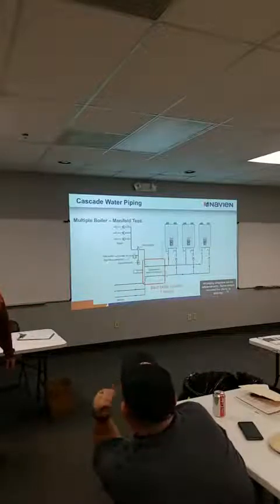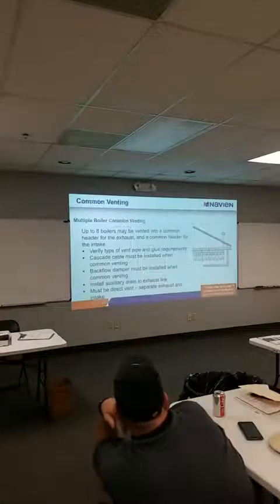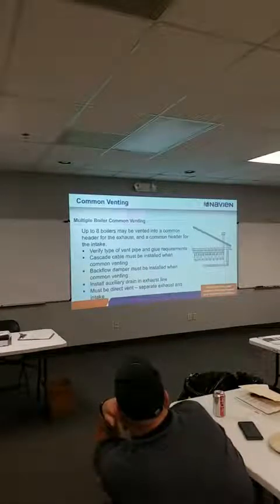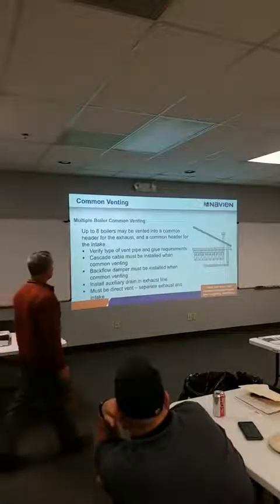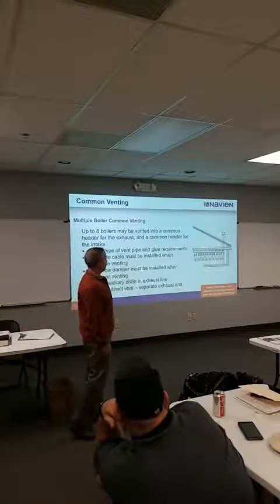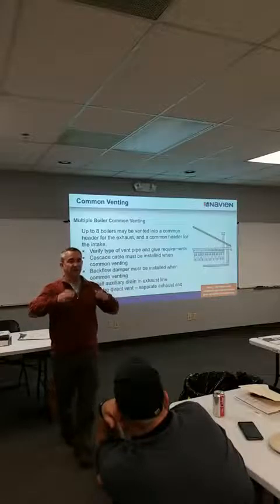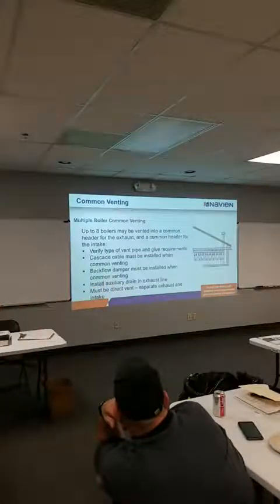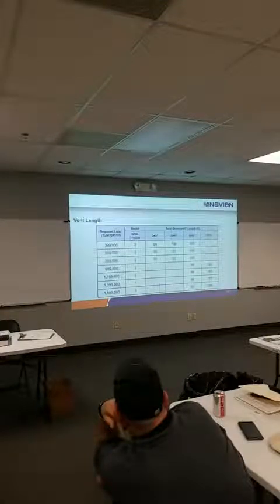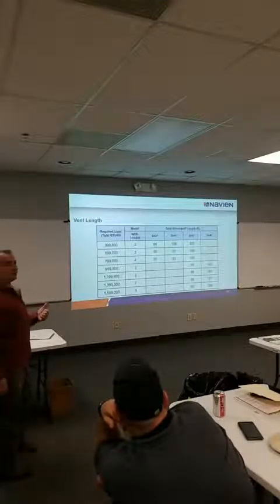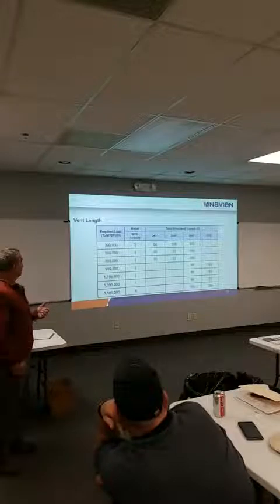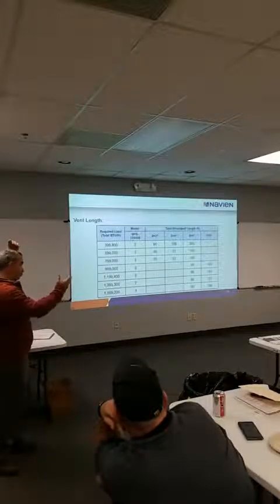Temperature sensors with the sensor. And again, you'll see where the vent damper kicks in, you have to put that little condensate T in and drain everything back to that condensate T at that point. So when you're doing multiple units, we do upsize the manifold for the intake and the vent. And this chart's in your book. And then all the same rules apply after that.